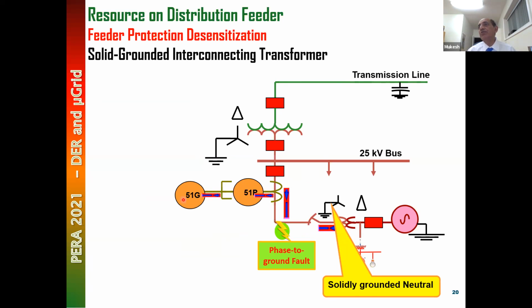And if this source is very strong and this transmission line happens to be very long, for a weak source here, this protection may not see this fault and may not clear until this opens. So that's a challenge. That's the biggest challenge, or it may not provide a backup for some other faults here. If this fault current becomes so low that this protection will not operate, that's not acceptable.